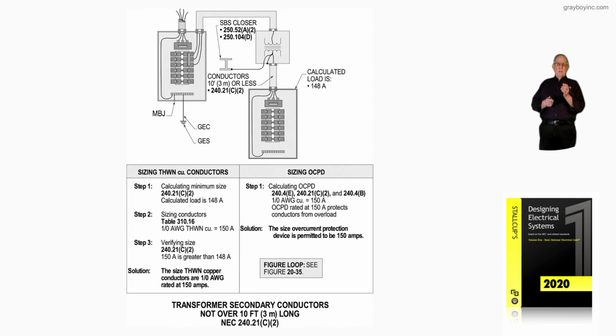And if you were having trouble tripping that 300 amp main you see, then you could go from 125% of the primary current to size it up to 250%, or whatever total percentage in between there that would allow that circuit breaker to prevent nuisance tripping, or tripping when you energize the transformer if it hadn't been electrically magnetized from the manufacturer. So figure 9-27 illustrates such a tap.